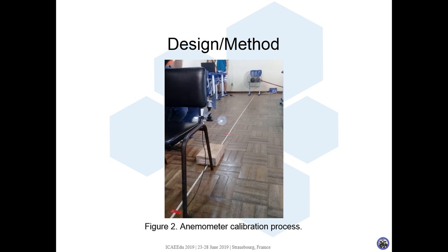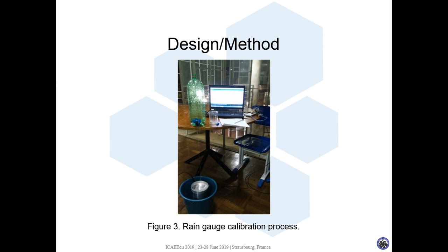For the sensors' calibration process, climatic conditions were simulated. The anemometer, for example, was set in 12 different positions in relation to a static fan. For each position, 30 measures were taken. This data was analyzed and compared to another device with superior metrological characteristics. The intensity levels of the investigated variables sought to match the already known classifications.